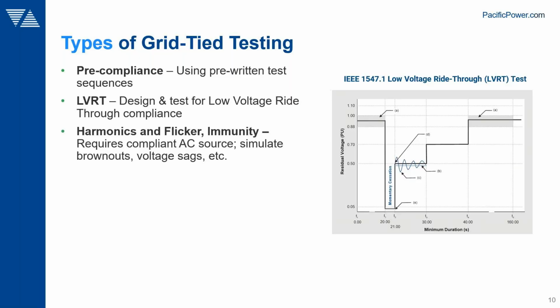Other test requirements, particularly for products exported to the European market, must meet CE mark requirements. That includes, among many things, harmonics and flicker immunity testing, as well as voltage disturbances, covering both emissions and immunity tests for power grid conditions. You can do this pre-testing yourself, and then if you need certification, you can go to a certified test lab and have them rerun the test on your EUT. So pre-testing in your own lab can be beneficial and a time saver when you go to the actual compliance tests.